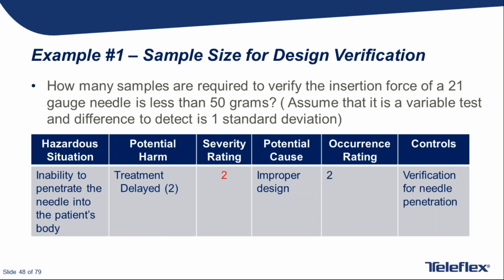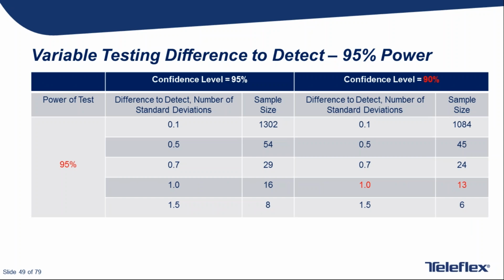So real quick, I'm just going to review through an example to reinforce the concepts. I'd like to show another contrast between variable and attribute testing, and then follow with a more detailed real example from experience where we're using some different and enhanced tools. This time I'm just going to quickly present variable testing first, and this is about verifying an insertion force versus a requirement. If the insertion force is too high, the needle cannot penetrate the patient's body, treatment can be delayed, no serious harm, so the severity rating is 2 on the 1 to 5 scale. And the severity rating of 2 leads us to a 90% confidence, 95% power situation.